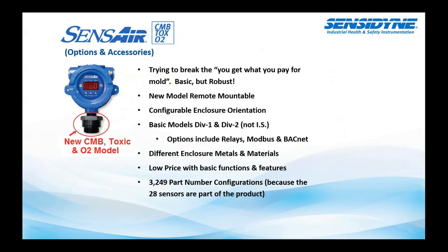And again, the SensAir, this is trying to break the 'you get what you pay for' mold. It's a basic unit, but it's very robust. It has 28 different sensor options for toxic, O2, and combustible gases. And you're around the $1,000 range on this. This is a very economical transmitter and sensor package. You can remote mount the sensor. It does have relays, 4 to 20 milliamp output, and BACnet if that was something you were using, as well as Modbus options. So lots of options, lots of benefits and features at a very competitive price.